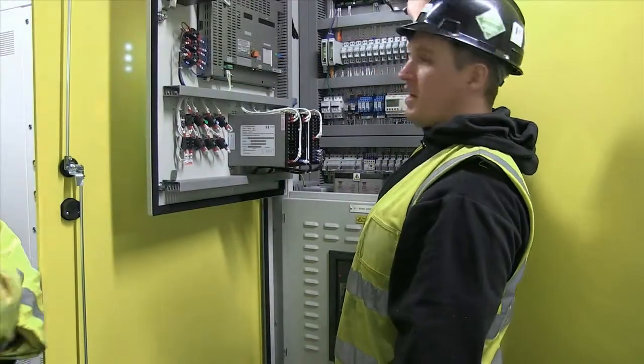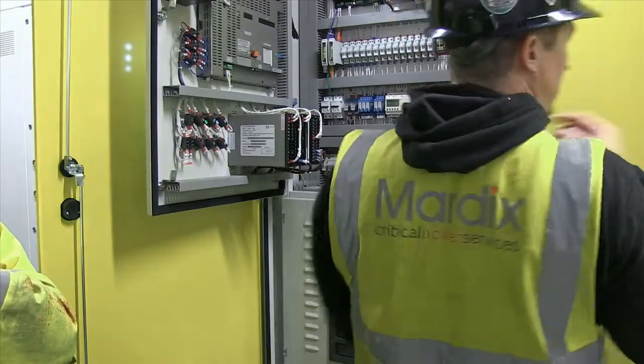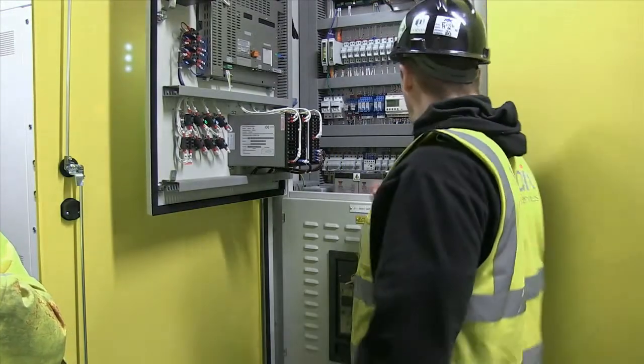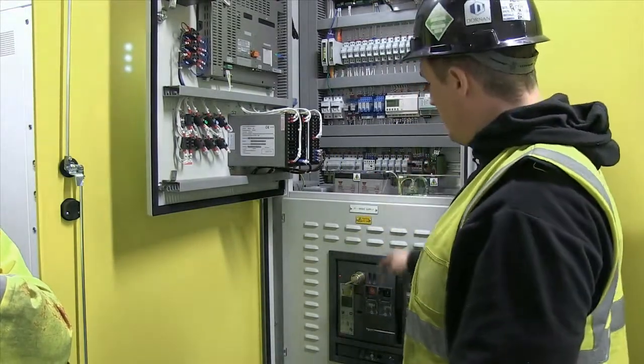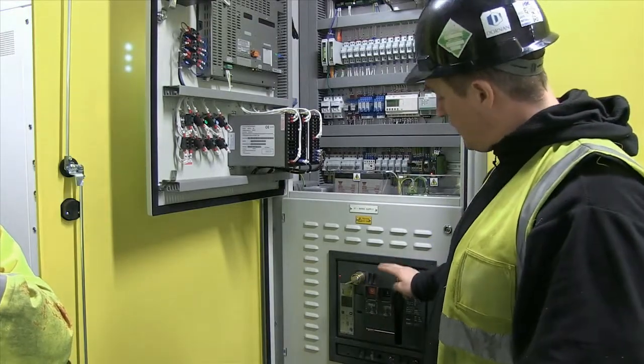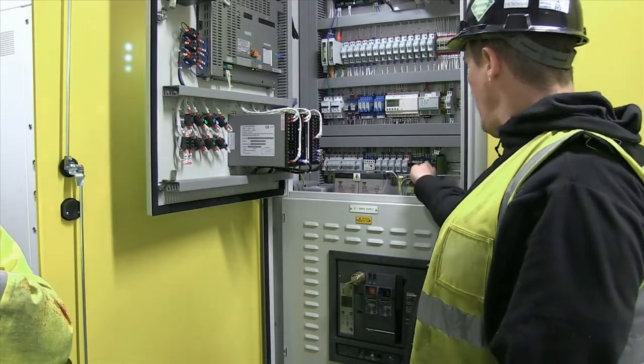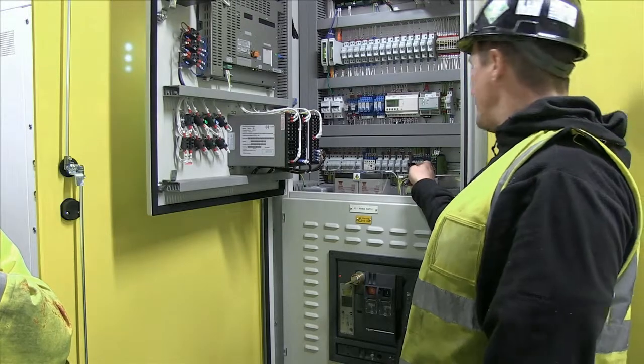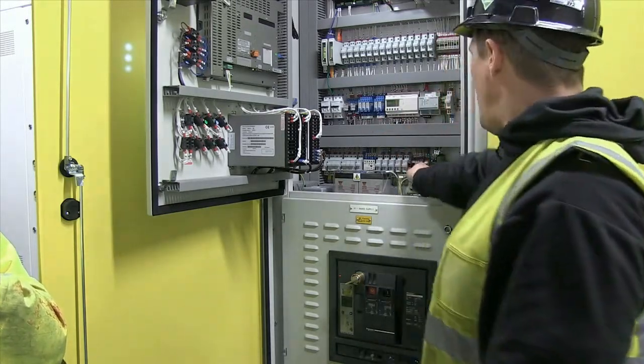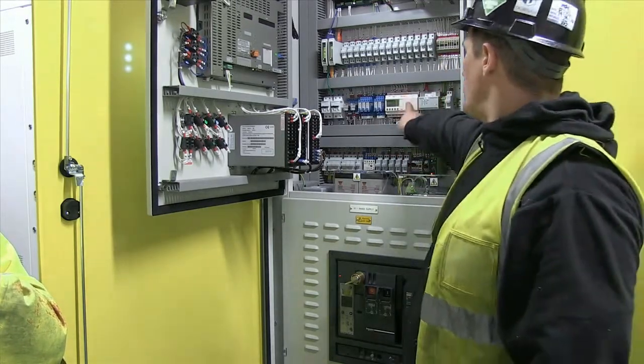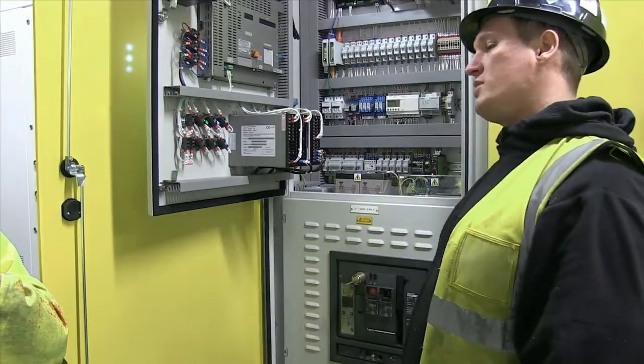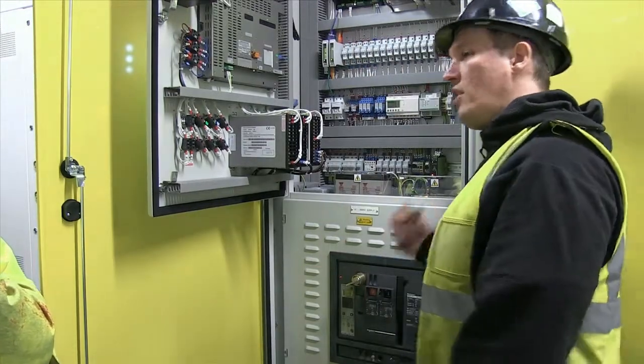PLC, that's what does all your monitoring of all the breakers. Mains failure relay again relies on the incoming side of this breaker. So if that was in the fault, basically, if you lost mains, that would see it, that would go off, that would start that off, send your generator start signal, generators would come on and confirm.